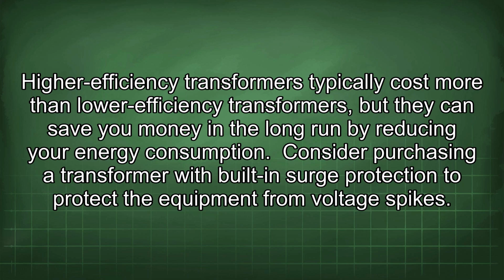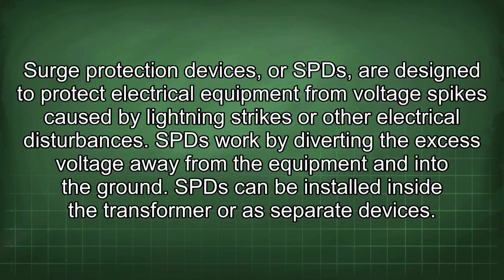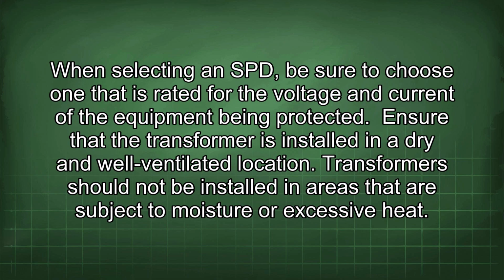Consider purchasing a transformer with built-in surge protection to protect the equipment from voltage spikes. Surge protection devices, or SPDs, are designed to protect electrical equipment from voltage spikes caused by lightning strikes or other electrical disturbances. SPDs work by diverting the excess voltage away from the equipment and into the ground. SPDs can be installed inside the transformer or as separate devices. When selecting an SPD, be sure to choose one that is rated for the voltage and current of the equipment being protected.